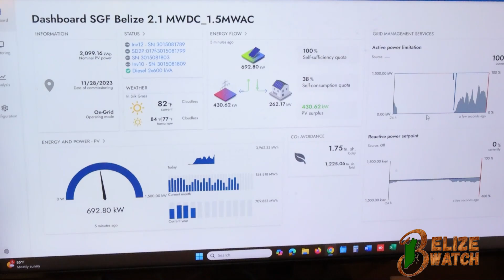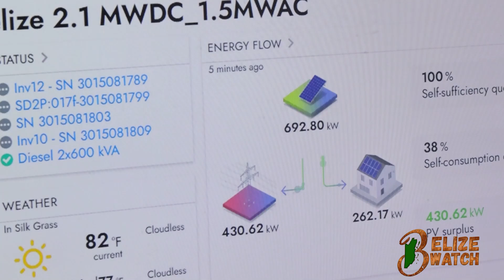So this information here shows 2,099 kilowatts - where's this coming from? That's the system information. Here you can see what the solar system is producing right now, 692.80 kilowatts. Of this, are you using it? We're exporting 430. The facility is using 262 - so you're exporting more than you're using right now.